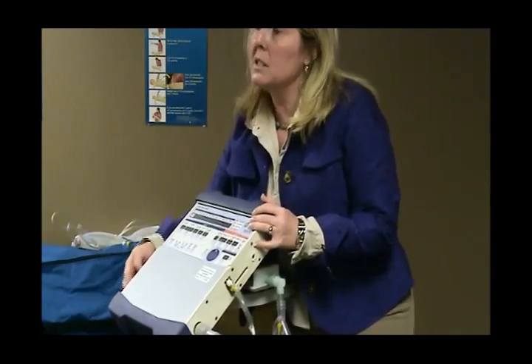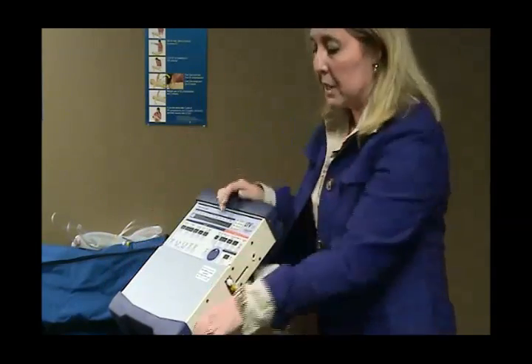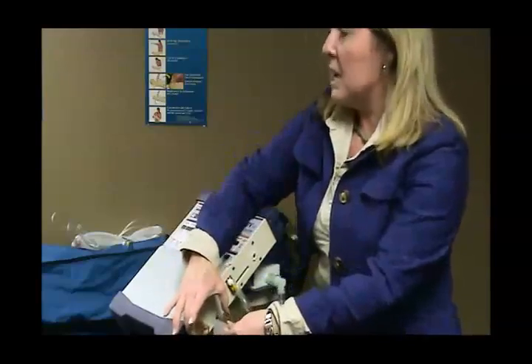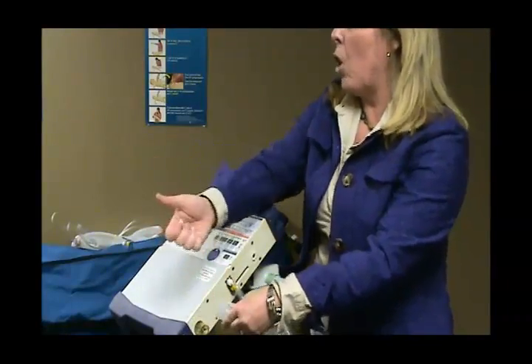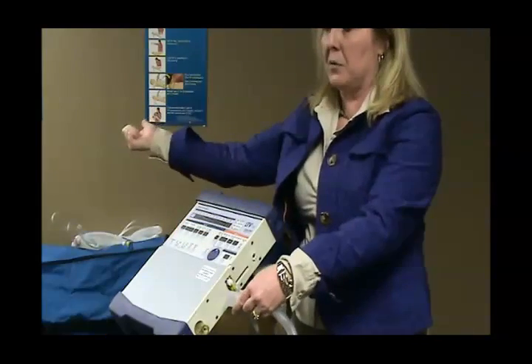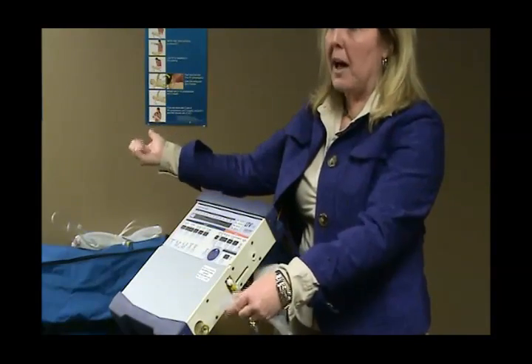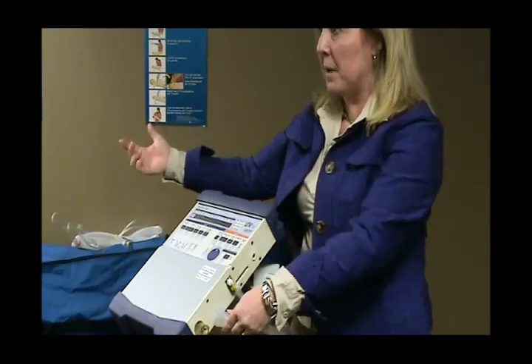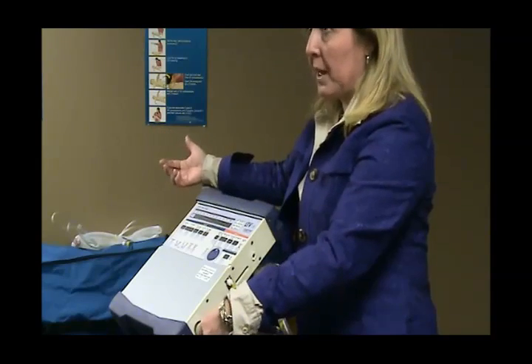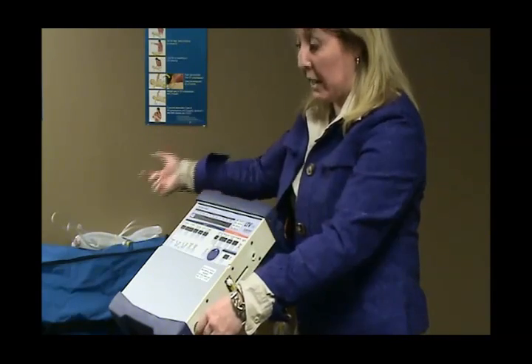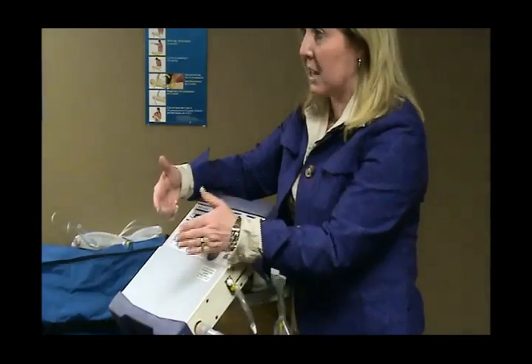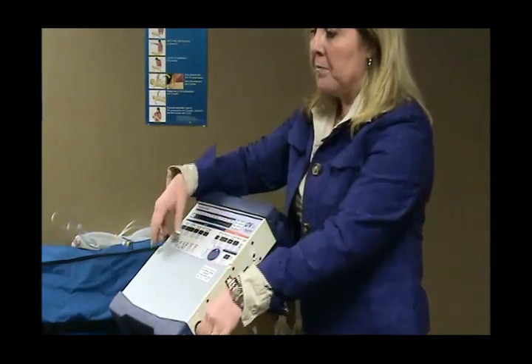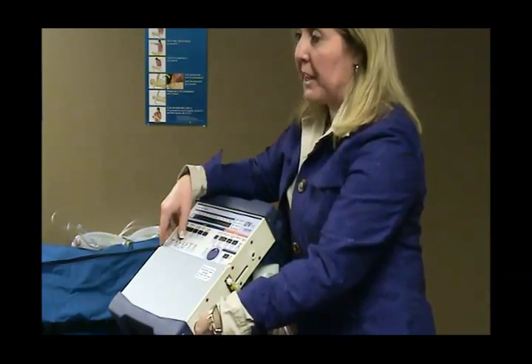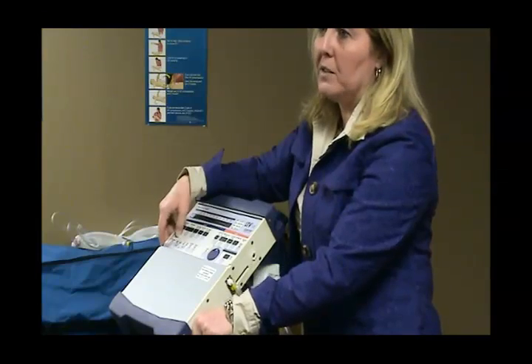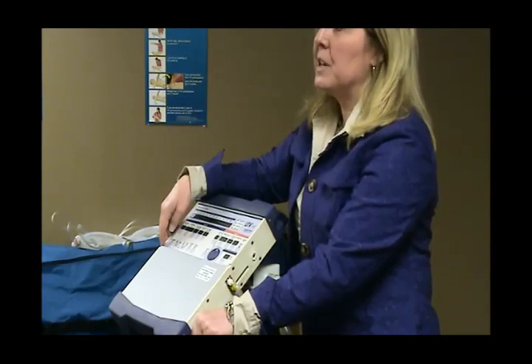The biggest reason that I like to go over this with people is that on that filter that sits here, sometimes you will see a gray dust build up on the ventilator side of the filter. That freaks people out. I'll admit, it freaked me out the first time I saw it. I was like, what the heck is that? And what is on the inside of the ventilator, because that's coming from the vent. After freaking out for a few seconds, I called tech support and they said, one of two things.